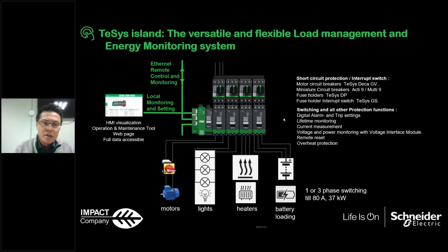So how can we do that? Before we talk about that, you can also use the TeSys island not just for motors. You can use it to monitor all of the other loads. We have other modules, not just starters. We have a PCB board, the power interface module, that you can use to monitor the lighting system, the heating system, and the battery loading. So it is not just controlling the motors or monitoring the status of the motors. You can also use the TeSys island to monitor the energy or the status of other loads, like lighting, heaters, and battery loading. So this is not just motor management, but load management.